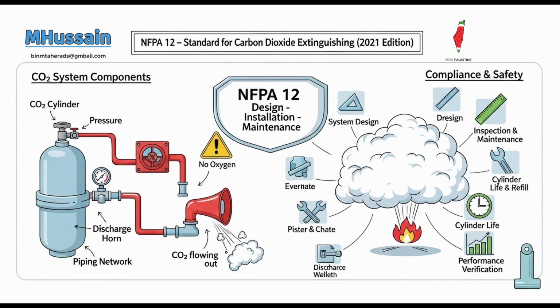Right. In fact, in total flooding systems, CO2 can still protect adjacent ordinary combustibles or be used if these reactive metals are already covered by another material, like sodium stored under kerosene. So it can protect around them. It can. But for local application systems, which use a high-velocity directed discharge, it's especially important to avoid direct application onto these reactive materials, as the force could potentially spread them or exacerbate the situation. Got it. Don't blast the burning metal. Basically, yes. So it's not just about what it can put out, but what it can't affect or even inadvertently harm. That's a vital distinction.